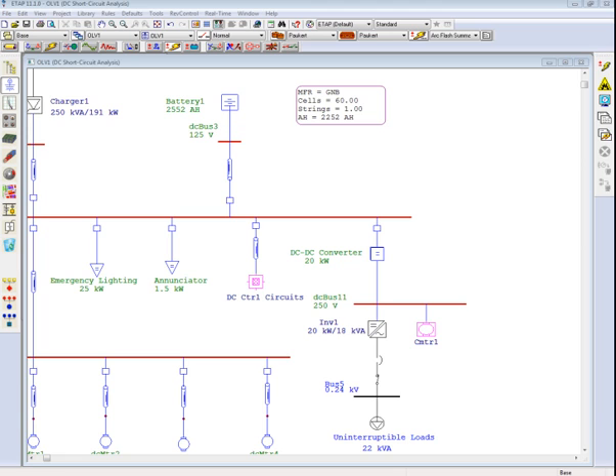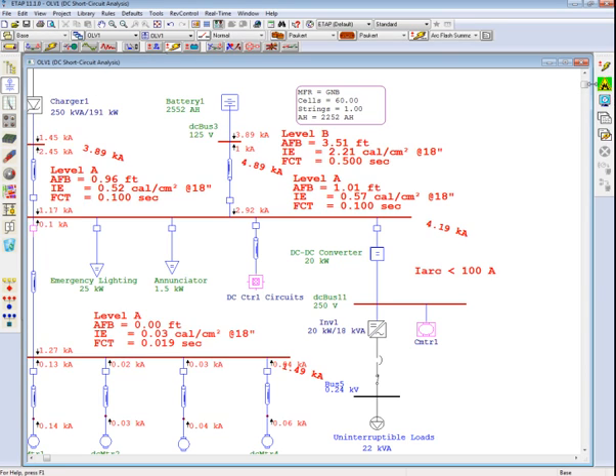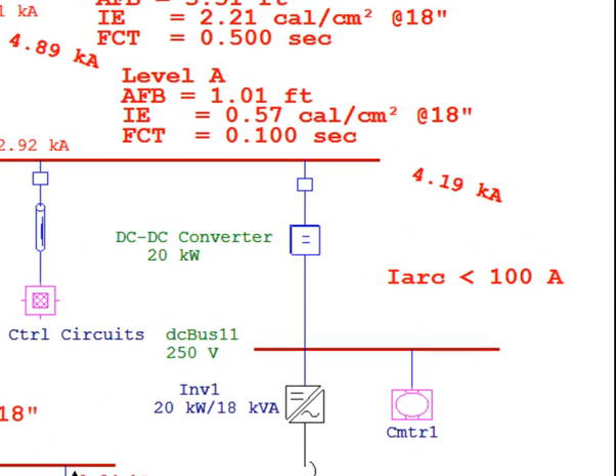Let's go back to ETAP and run the Paukert method. At DC Bus 11, a message stating that the arcing current is less than 100 amps is displayed. This is one of the limits of one of the equations within the Paukert method. This method attempts to model the system more accurately when compared to the results produced through the maximum power method, where an arc fault is always assumed to be sustained.